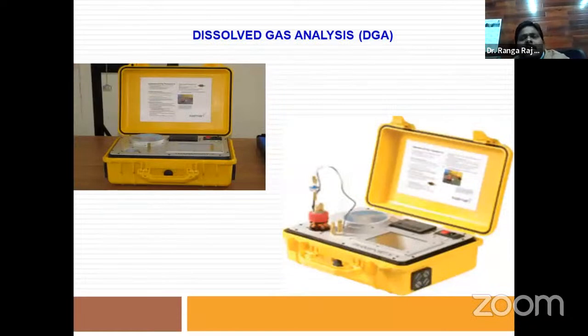The next test is dissolved gas analysis, which I already discussed. We keep the oil in this red color bottle. Performing tests on oil is very easy compared to paper. We can collect the oil with a test tube from the transformer's outlet valve, simply connect the test tube and a syringe, and take the oil out, so we can perform various tests on the collected sample.